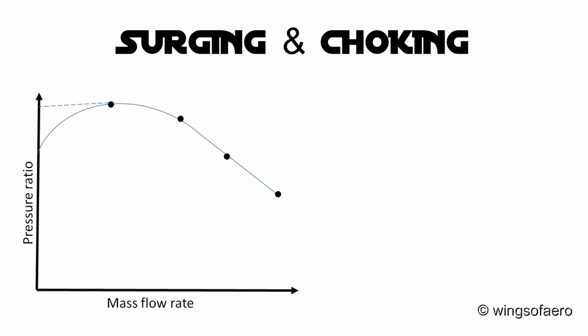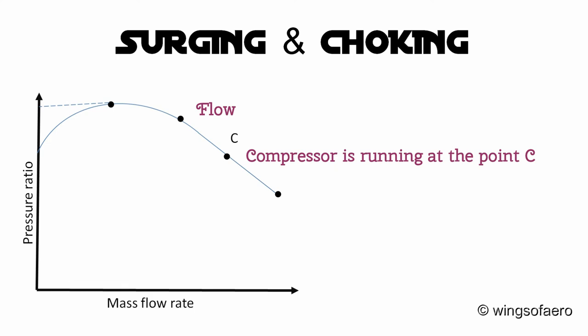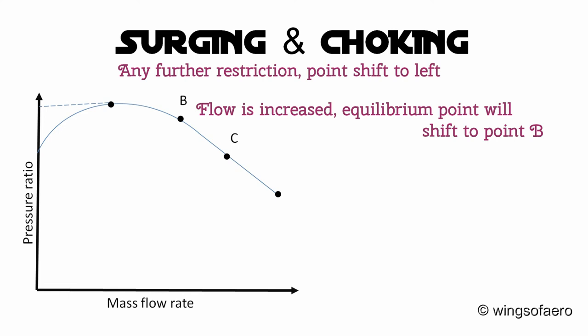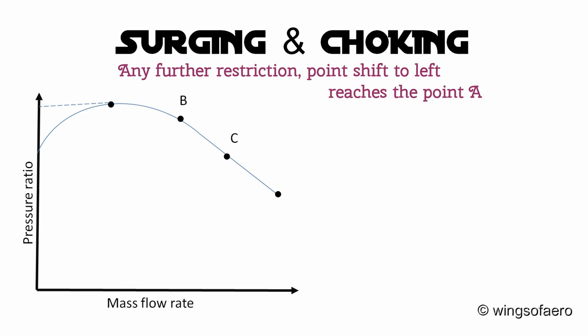Surging and choking: A typical characteristic of the compressor at one particular speed is shown in the figure. Assume the compressor is running at point C. If resistance to flow is increased — for example by closing the delivery valve — the equilibrium point shifts to point B. Any further restriction shifts the operating point further left, ultimately reaching point A, where the maximum pressure ratio is obtained.